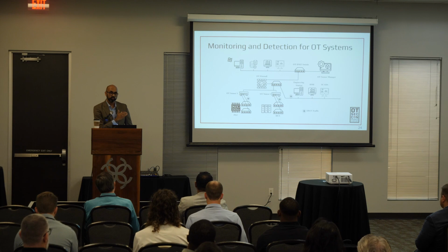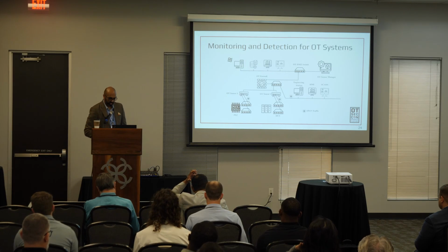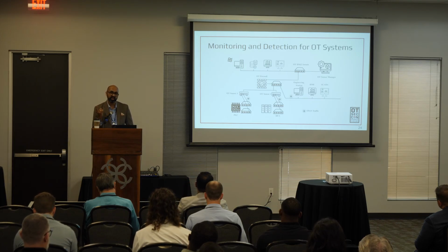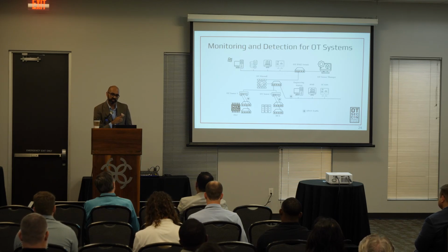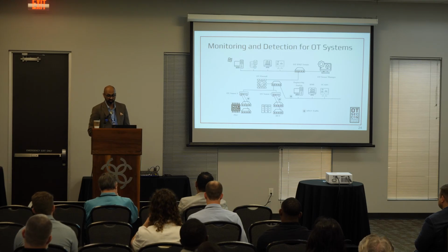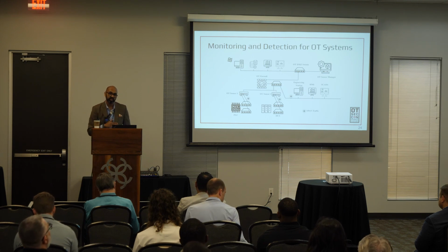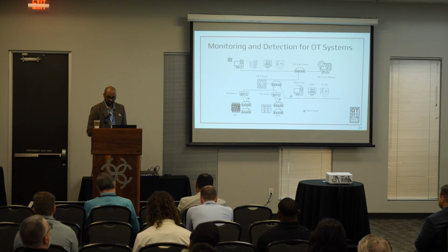These OT sensors are passively sitting and sniffing traffic at level 2, which is most of your DCS, PLC traffic. They are mirrored traffic. They're not actually talking to these devices. They're just looking at the mirrored traffic and are able to say if there is a new device that just started talking or there is some kind of configuration change going on. Again, depending on the vendors that you choose, they will have different capabilities, but do a POC. Make sure you test it before you implement it. I think that was one of the themes of this morning's talk: don't just do it and leave it. Test it, make sure you have a plan for what you're going to get out of it.